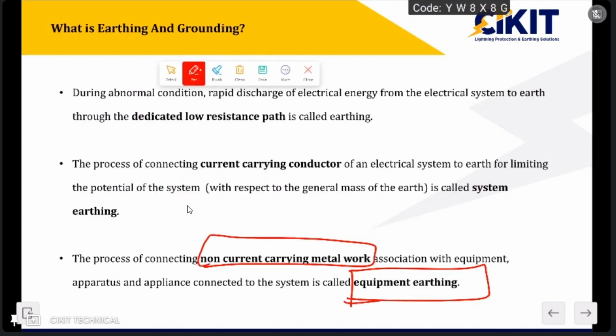The second type is connecting the current carrying conductor of a system. In a system, the neutral is considered a current carrying conductor. Current will always be flowing through the neutral, either unbalanced current or some other current. Some amount of current will always flow through it, so the neutral is considered the current carrying part of a system. If I connect the neutral of the system to the ground, it is considered system earthing.